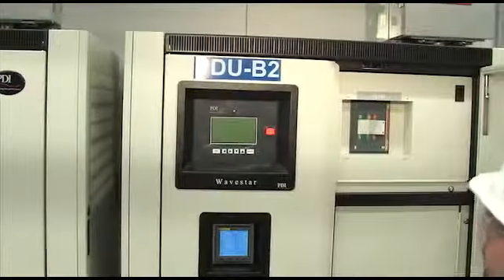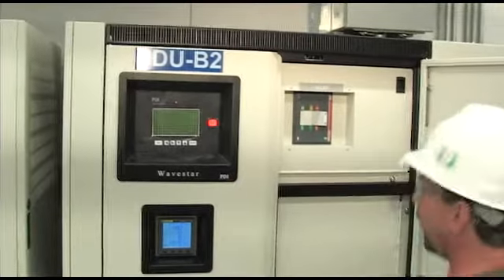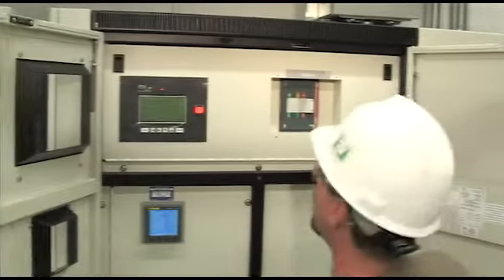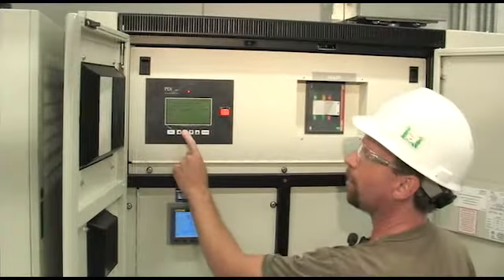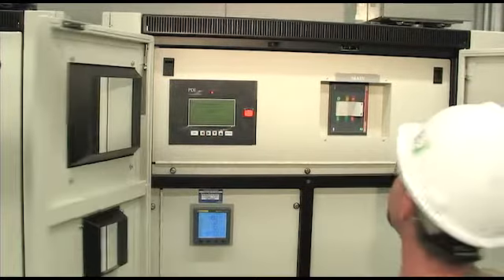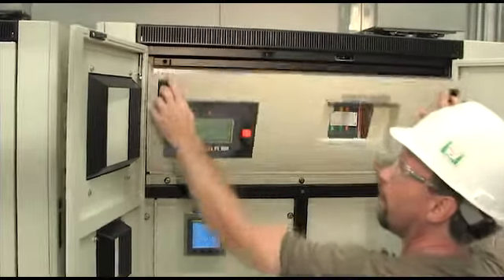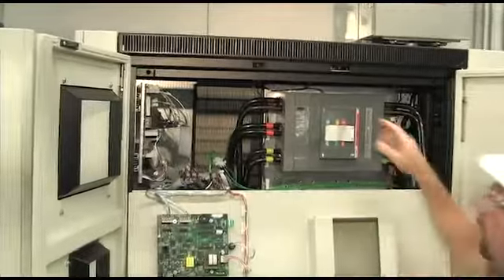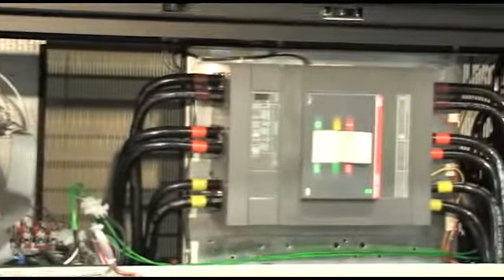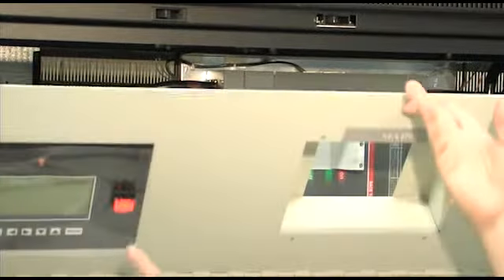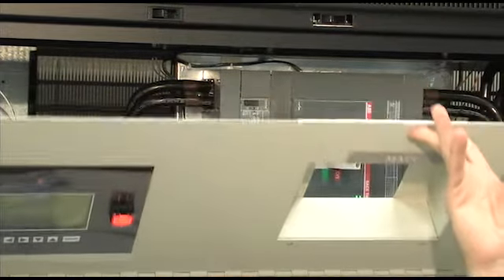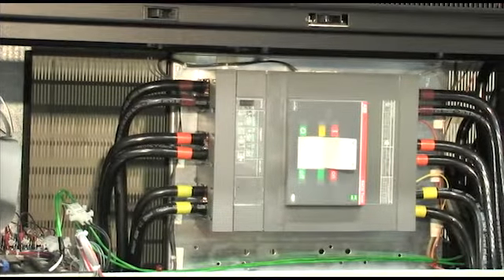So in this case, I'm just going to generate an alarm by opening the door. And I'll clear that in a moment. To stop the alarm sound, I press the right arrow key. And then just to go inside here real quick, you have the main input breaker. When you actuate the EPO, the emergency power off button, it will trip that breaker.